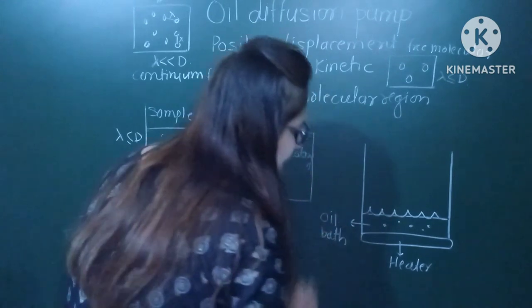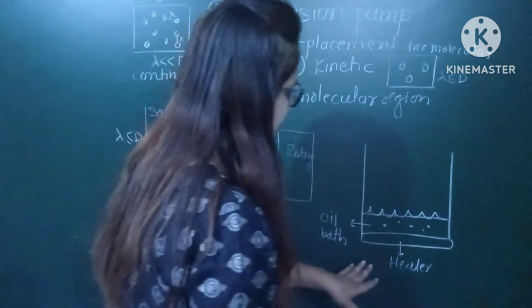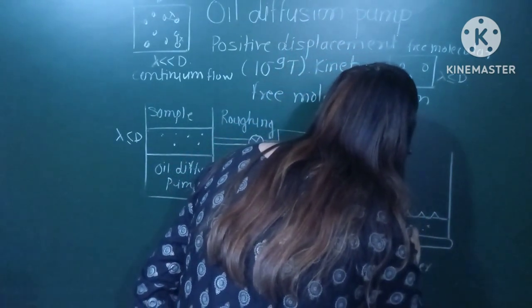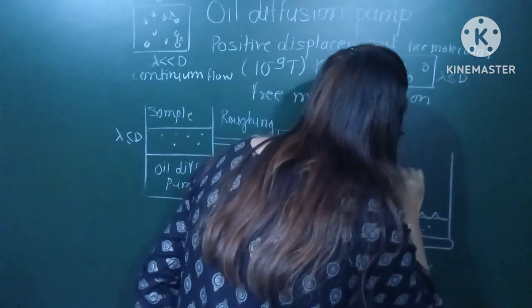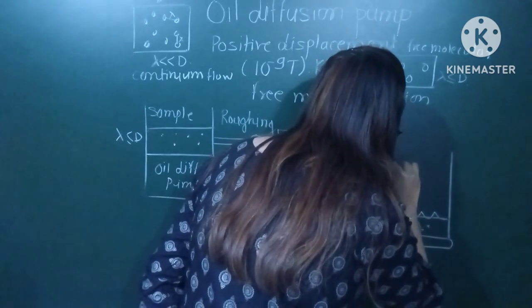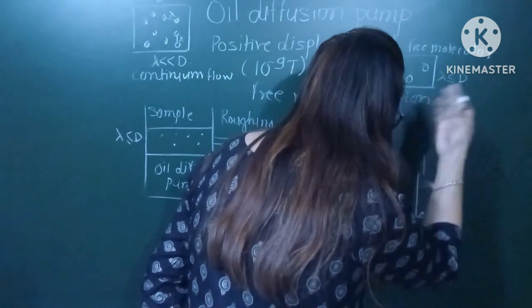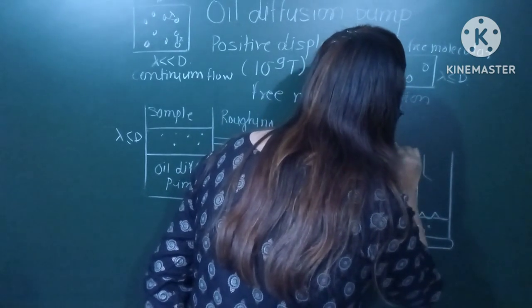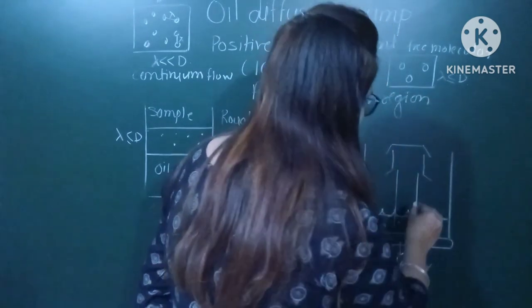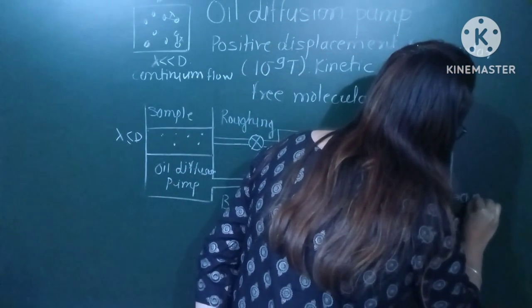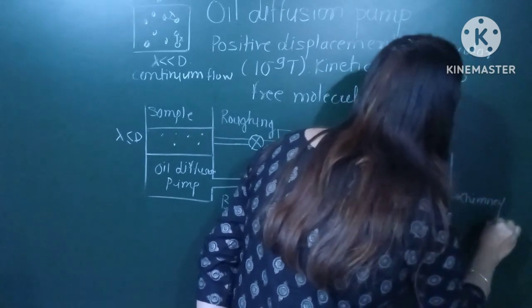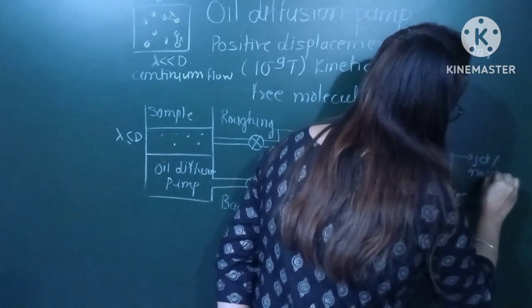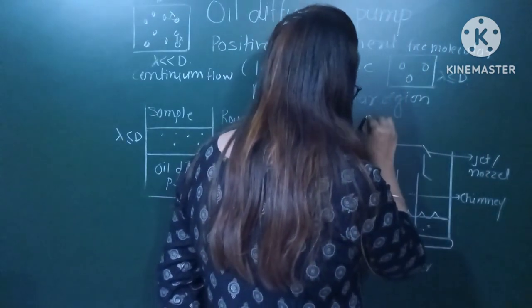This is a kinetic type of pump, so we must supply some energy. In the oil bath we have a chimney. The chimneys can be one stage, two stage, or three stage. At the top of the chimney we have a nozzle — this is the chimney and this is the jet or nozzle.